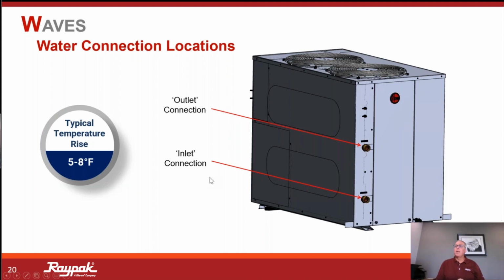And then again, we've been talking about those flow rates, a little bit higher flow rates than we might be accustomed to, but we want to see that temperature rise in this multi-pass system between the unit and the storage tank of a 5 to 8 degrees Fahrenheit rise. Again, that's why we're having these flow rates that are a little bit higher than what you would normally be accustomed to.